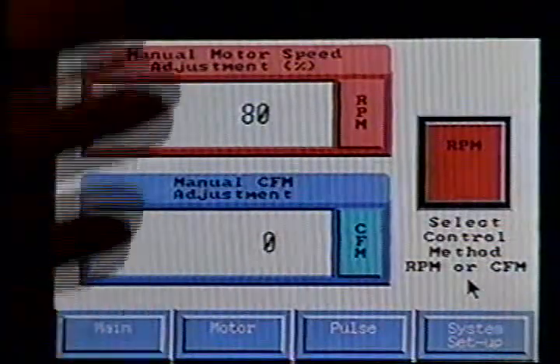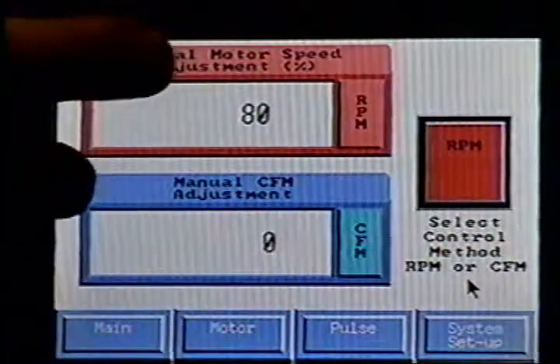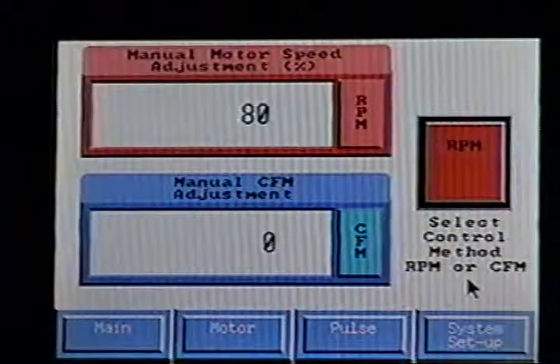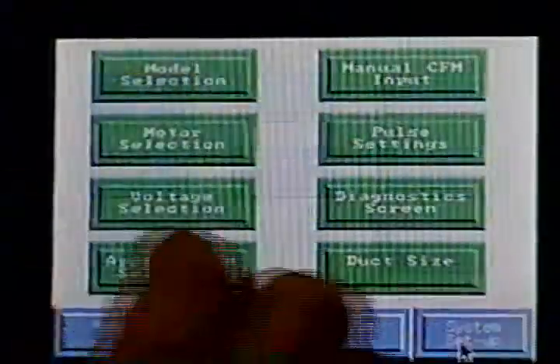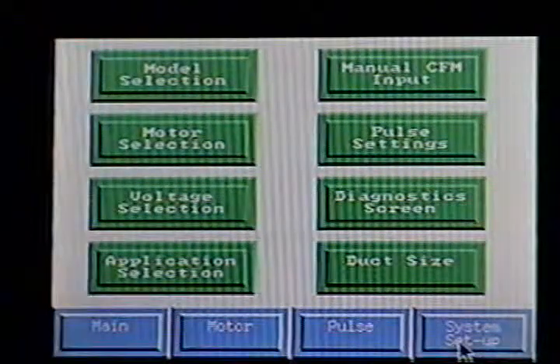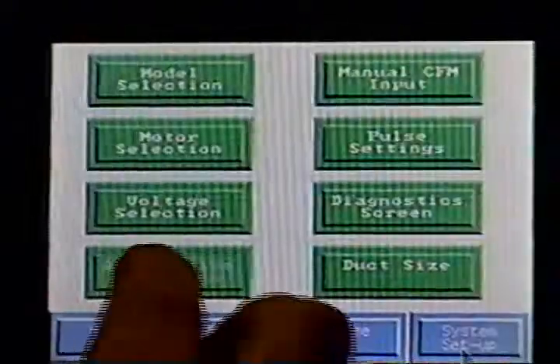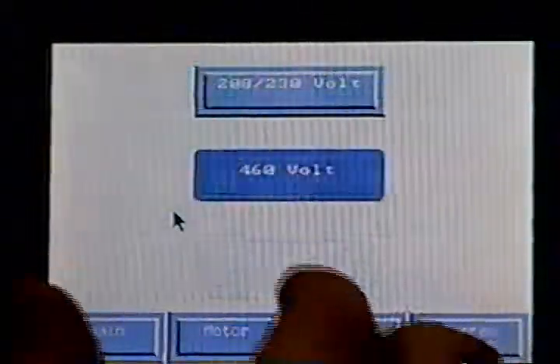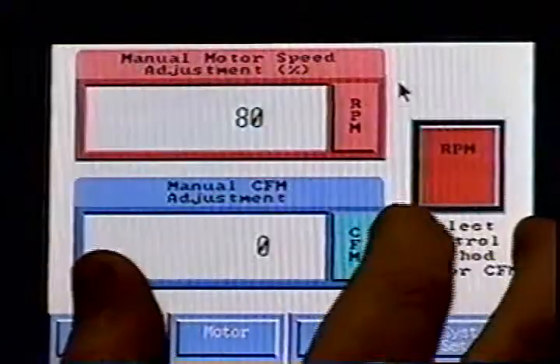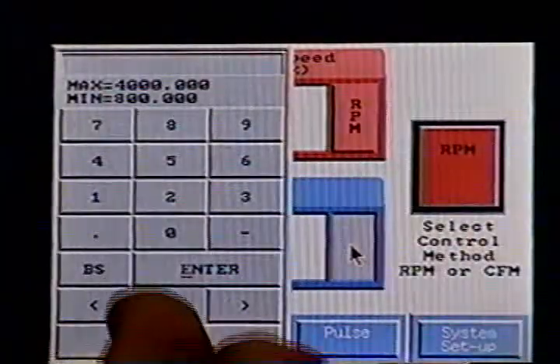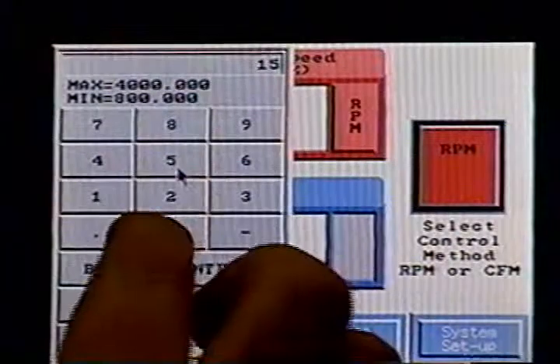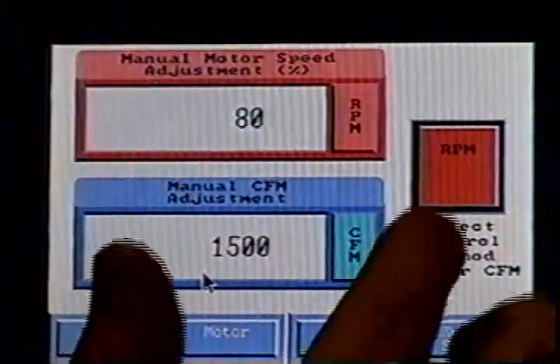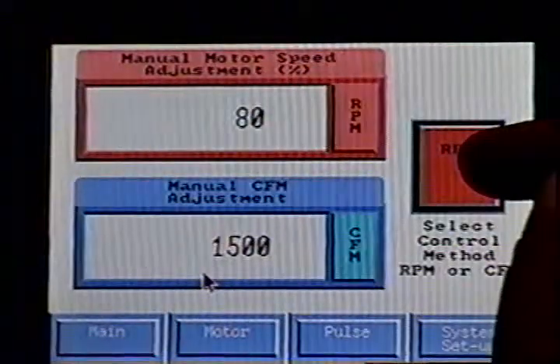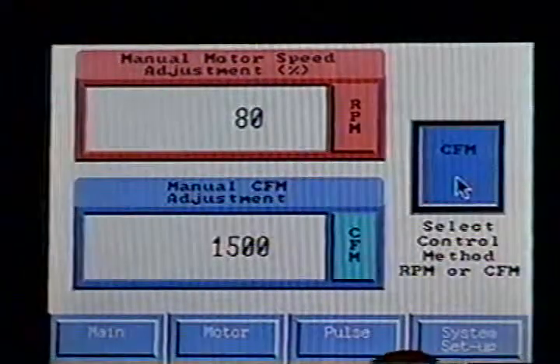Same screen. This is where we will control the CFM. Let's go in and make sure my motor is set up. I'm going to run through this real quick so I can show you the CFM, then we'll go back through the screen so you can see what all is going on. Let's say we want it to be 1500 CFM. Now it's in RPM mode, but I'm going to switch it over to CFM mode.